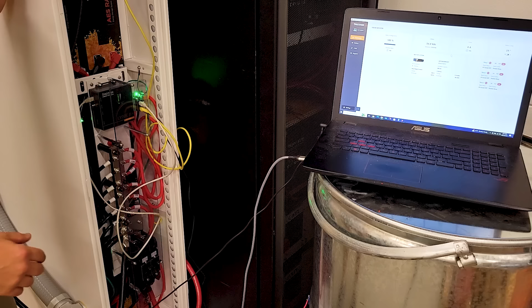Oh, something just clicked. One of these circuit breakers just tripped off right here, the one closer to me, which means everything's now going through the other one. And that's at 4 minutes in, 4 minutes and 5 seconds. Now both tripped, so everything just turned off. We recently tested this cabinet trying to get it up to the 500 amp rating, and the circuit breakers popped at 468 amps after 4 minutes and 5 seconds.